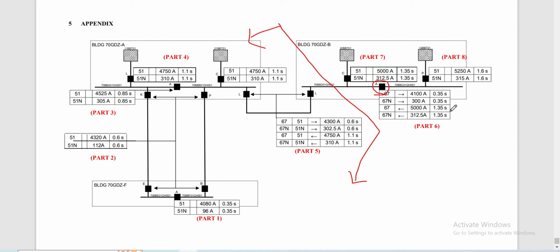Now, as what you have seen on the screen, the overcurrent protection on this bus coupler is only a directional overcurrent protection relay that we have provided here. So we have here the values already for our 67 relay in both directions. So we have this direction going to the left, and we have also these values going to the right.